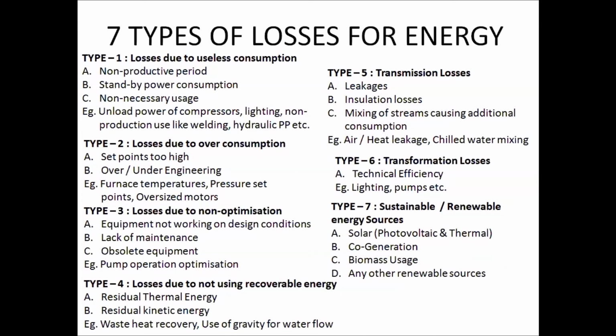Third is loss due to non-optimization, where the equipment is not working at its design condition. The simplest example is a pump: if it's oversized, you throttle it here and there to get the flow you want. If the pump is properly sized for the application, it will work the most efficient way.